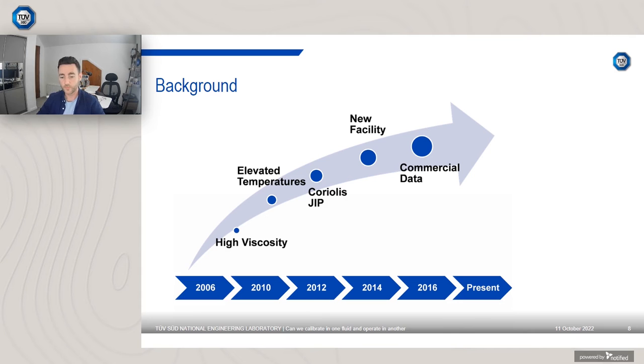We also decided that there was a requirement for higher viscosities, so we modified our facility via UK government funding from the flow programme to operate up to 2000 centipoise. Completed the JIP up to 600 centipoise, and we found that there was a significant viscosity effect with a variety of flow meters. That answered the question about viscosity.